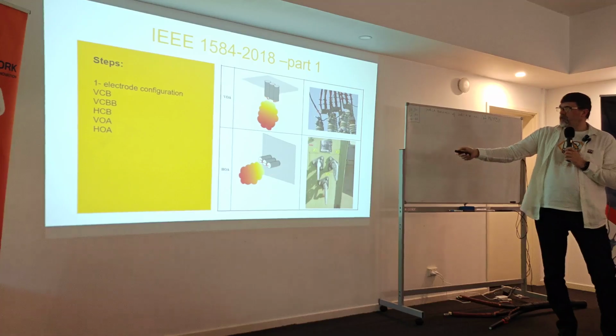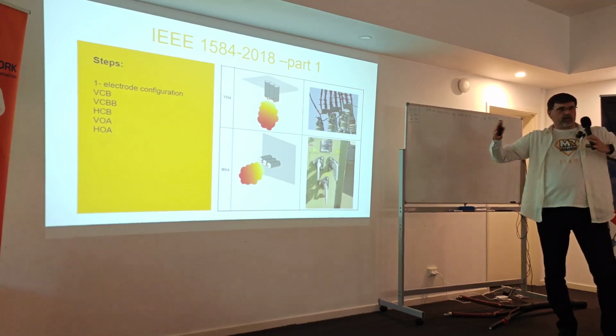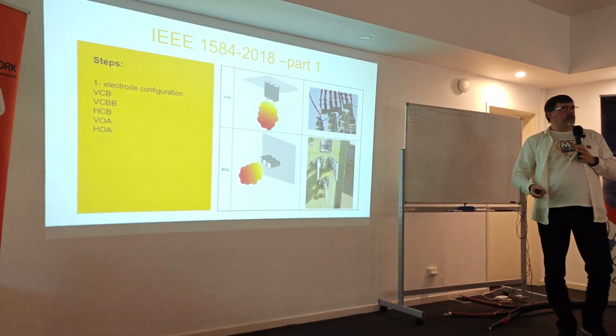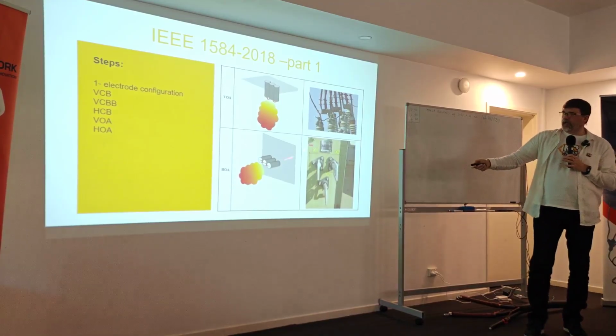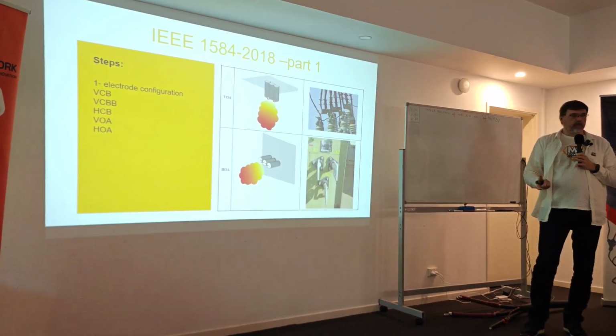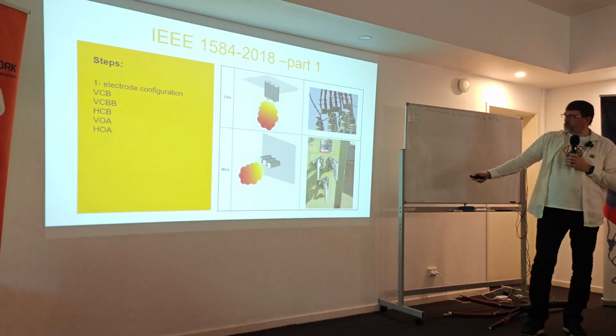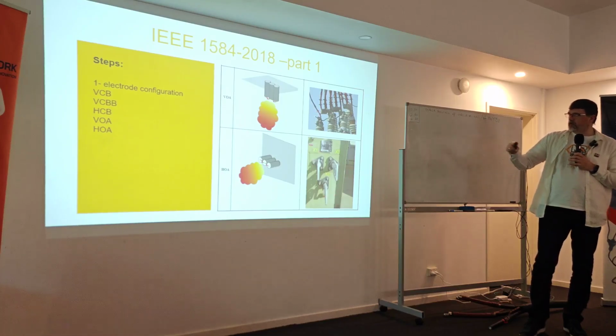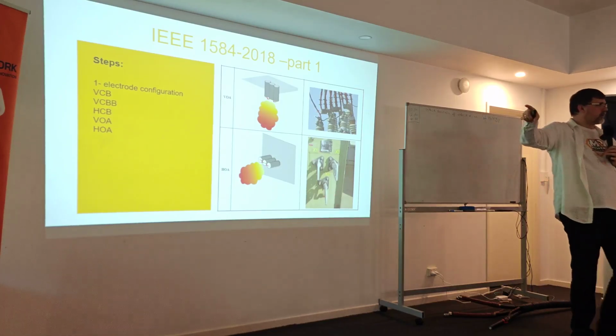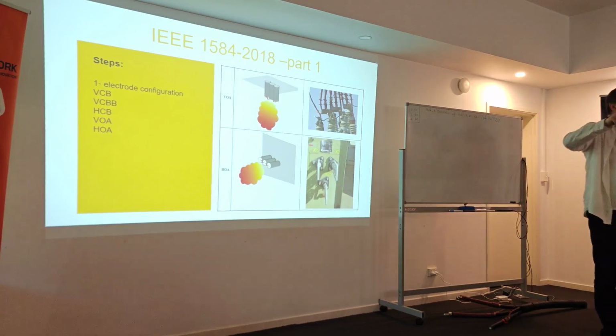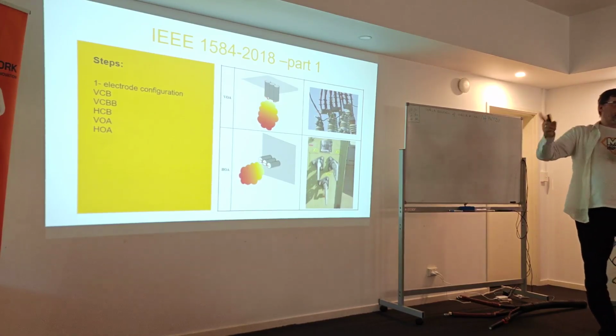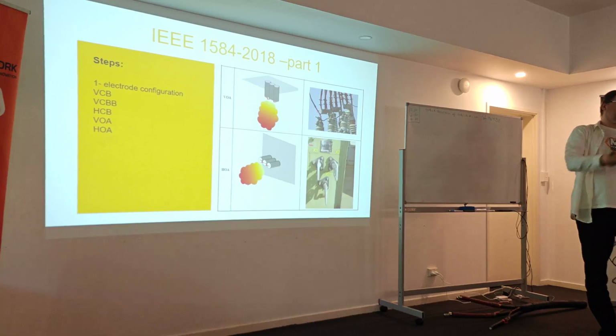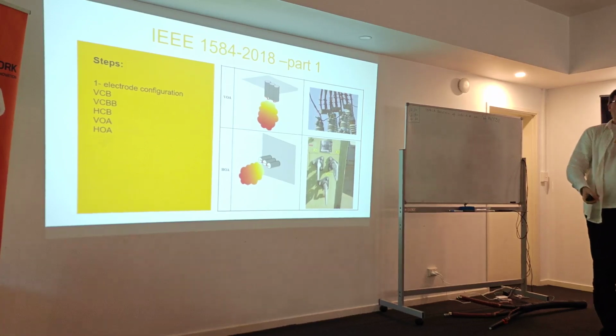VOA, HOA is the same thing, just in open arc, so there is no enclosure around the panel, and you will see a small difference because in IEEE there is nothing like the in-between. Like this, for example, this will have a different transmission factor in the DGUV calculation that Germany does, because it was full enclosure, partial enclosure, and open arc. In IEEE it's like enclosure or open, yeah? There's nothing in between.